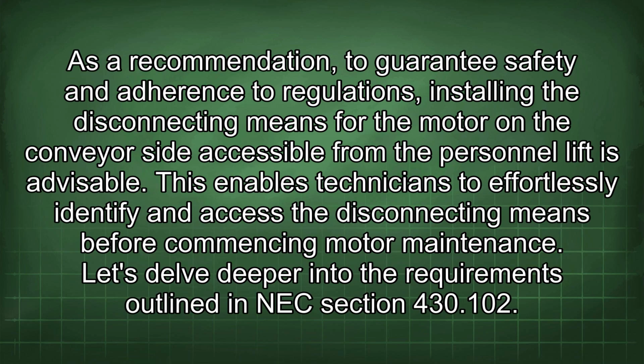As a recommendation to guarantee safety and adherence to regulations, installing the disconnecting means for the motor on the conveyor side accessible from the personnel lift is advisable. This enables technicians to effortlessly identify and access the disconnecting means before commencing motor maintenance.